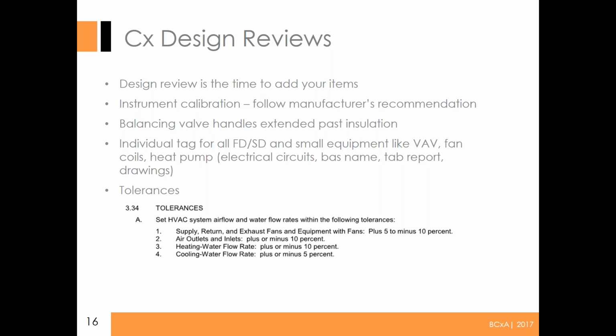Individual tag for all fire dampers, smoke detectors - look for things that have to be touched by multiple trades. For instance, a VAV is mechanical, but it's also controls, it's also commissioning. Fan coils need power, heat pumps need power, smoke dampers need BAS, they need fire alarms. So if you have a project where they just have 6 sizes of fan coils and call them FC1 through FC6, it's really hard. So look for that, try to get that - everything's got a tag.